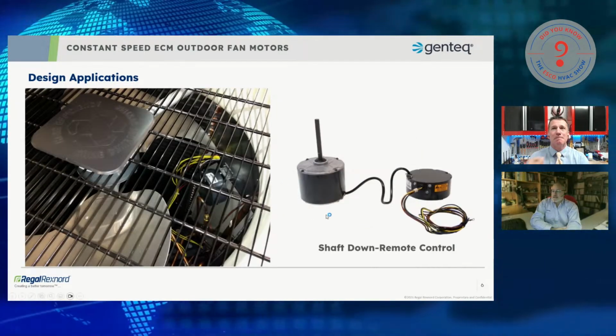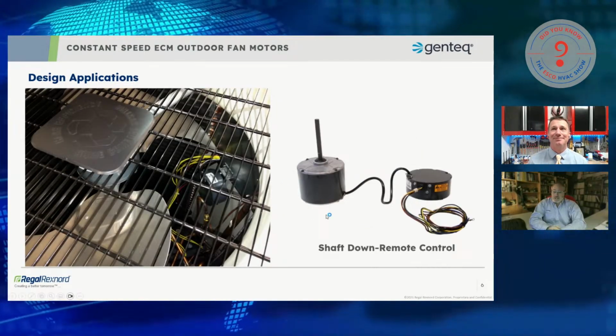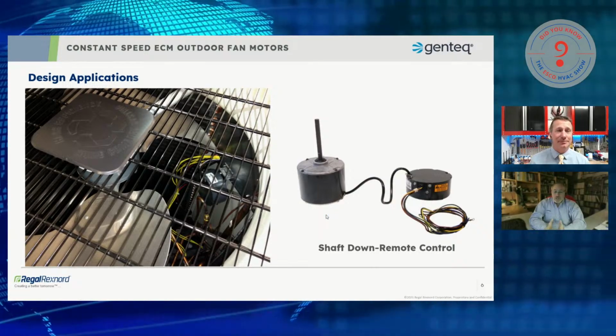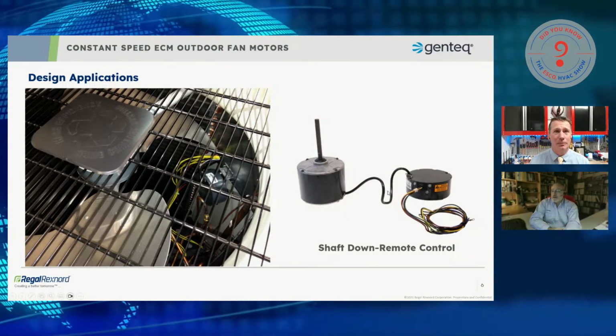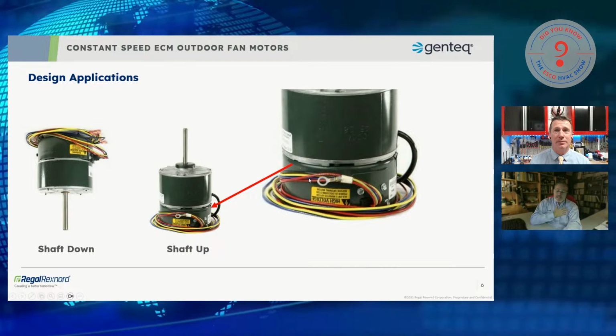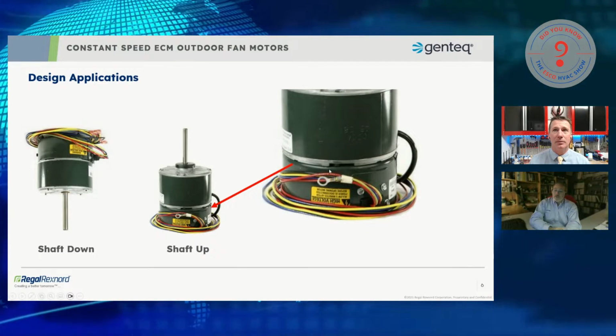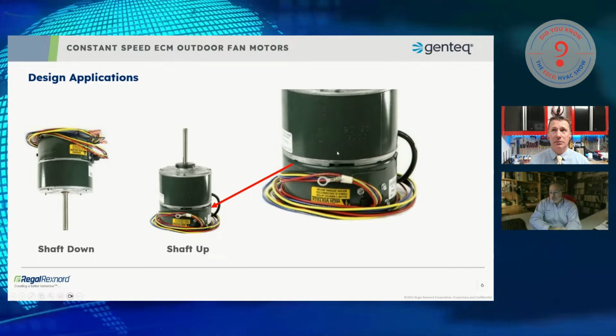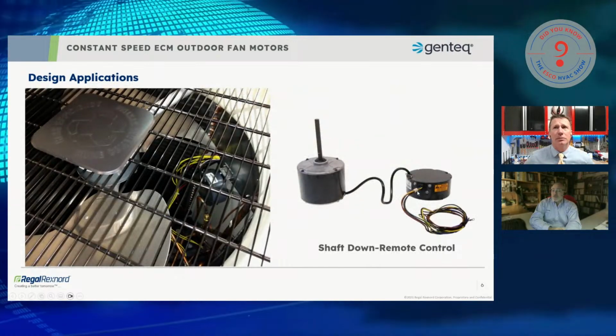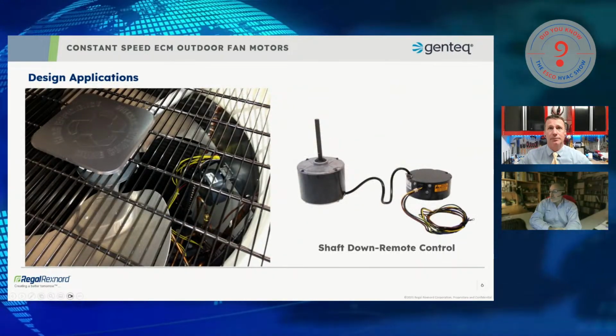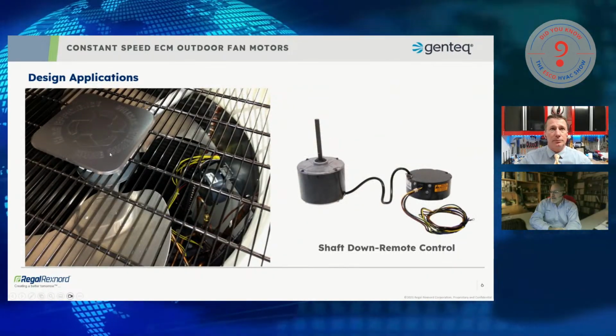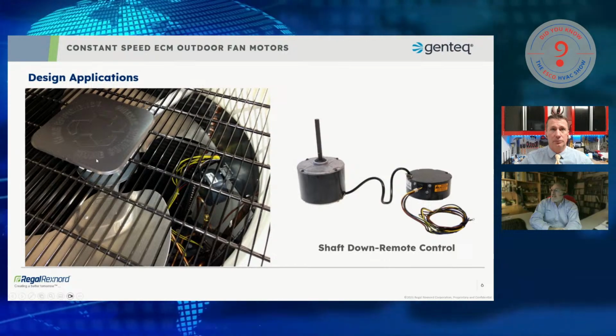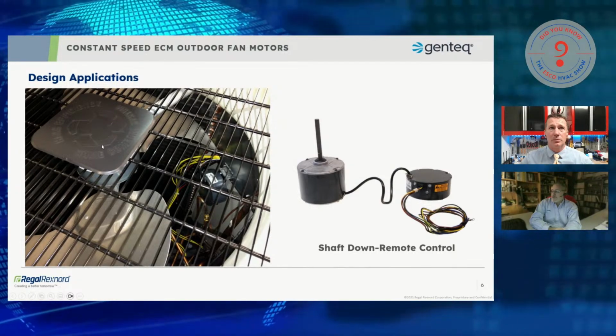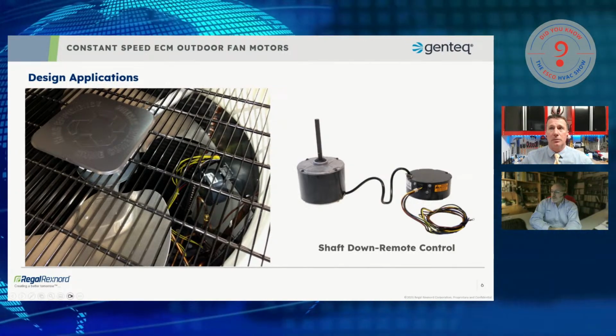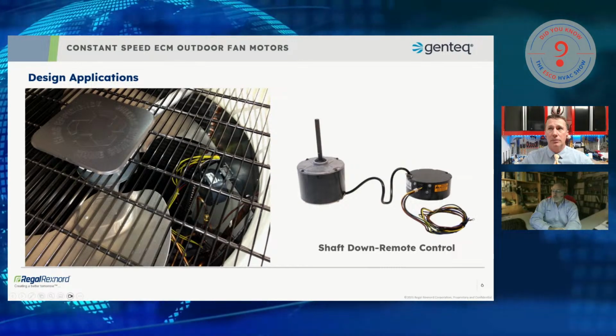And then last but not least, another design which we call the remote located or remote control. So the control is not mounted, I call it, maybe it's not the correct terminology, locally located. The control is located locally on the back of the motor. And this is a remote located control. So you can see in the unit here, the motor is mounted where it usually is. And then instead of the control being on the back of the motor, the wires go down and they go to the control, which is remotely located.